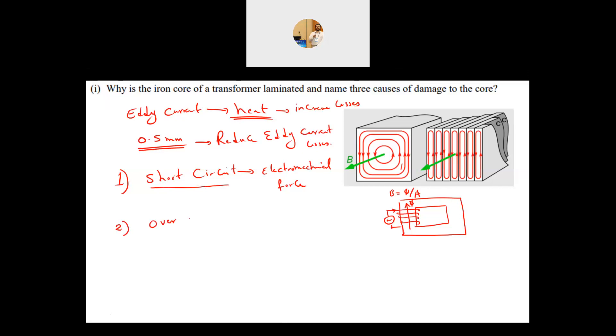The second cause is over-excitation. If you increase the voltage applied to the transformer beyond its rated value, you increase the flux density — this is called over-excitation. This causes saturation in the core, which leads to heating and can damage the insulating laminations between the core sheets.